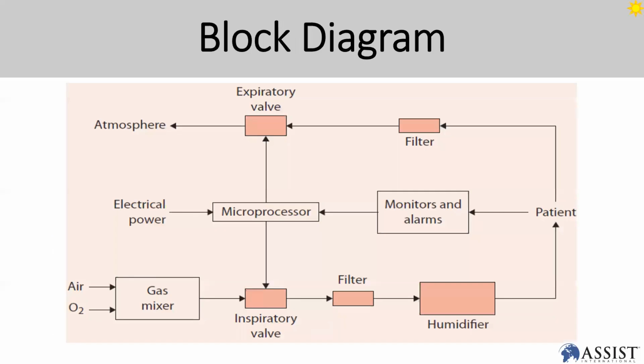So this is basically a block diagram structure. It's talking about air and oxygen coming into gas mixing and going to the inspiratory valve and flow. And there's a filter in between inspiratory and expiratory. And the inspiratory gas will go through a humidifier and go to the patient. At the same time, in between, there will be a microprocessor for the setting of the device for inspiratory breathing, and monitoring and alarm is to monitor the patient pressure, all that on the system.